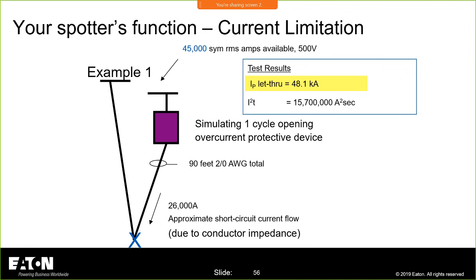And that's the peak. That was the magnetic forces, what contributes to flinging that conductor around. The I squared t is the heat, and that has to do with the duration of one cycle. And I let through 15.7 million amp squared seconds. That's a lot of heat.